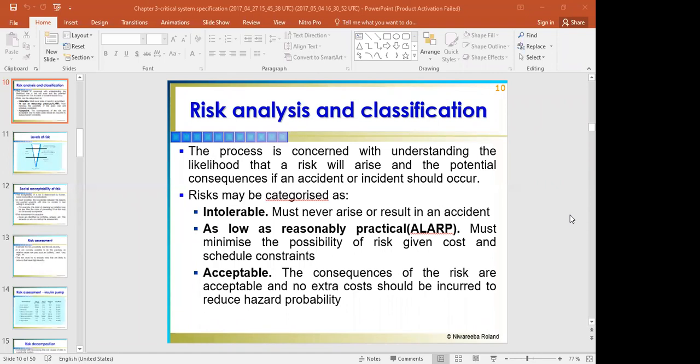For the insulin pump, the example of the acceptable risk is an allergic reaction arising in the user. The allergic reaction usually causes minor skin irritation. It's not something dangerous at all. So it will not be worth using special, more expensive materials in the device to reduce this risk. This risk shouldn't make someone spend so much money trying to avoid it, in this category.